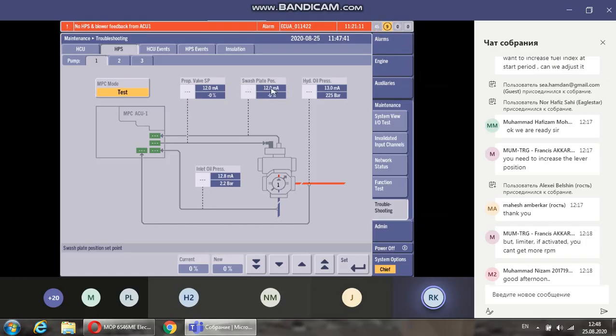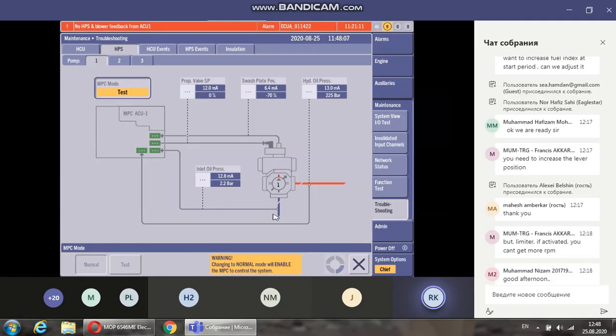You can also measure the amperages, as you can see, when we're getting a signal to move, the milliamp signal sent. So we can also go to the channel in the controller and check that the signal is coming through there as well. When I'm happy with that, I don't need to set it back to 0 or 10%. I can just press normal again, and then when we reboot, the controller will come back online in the normal mode, and therefore it is going to use the normal values from the engine itself.